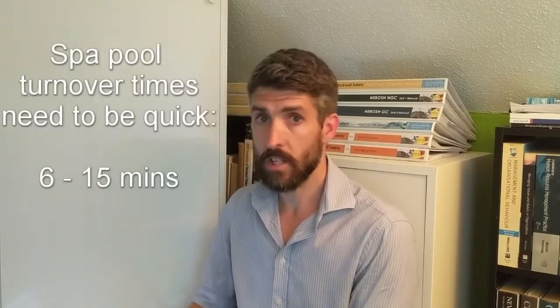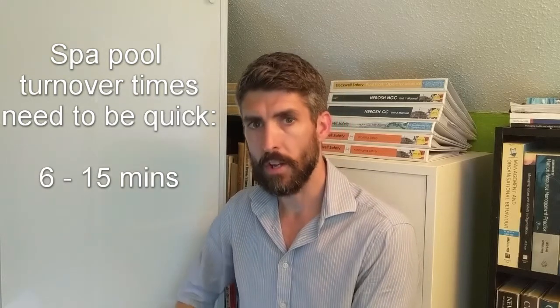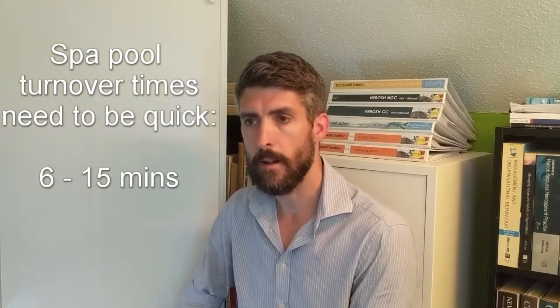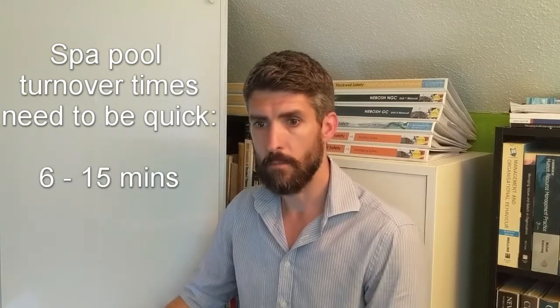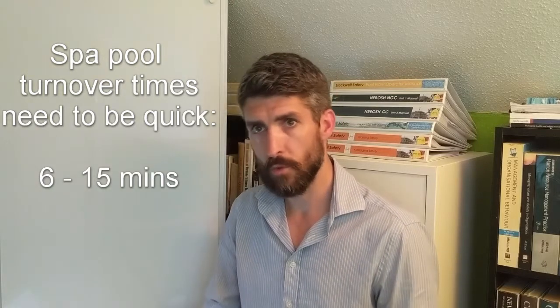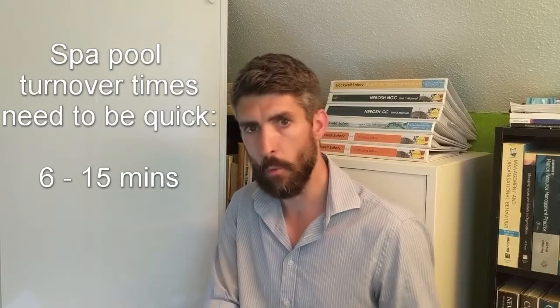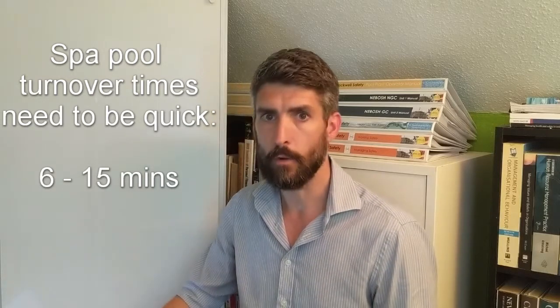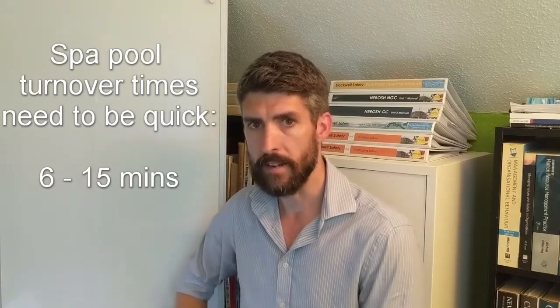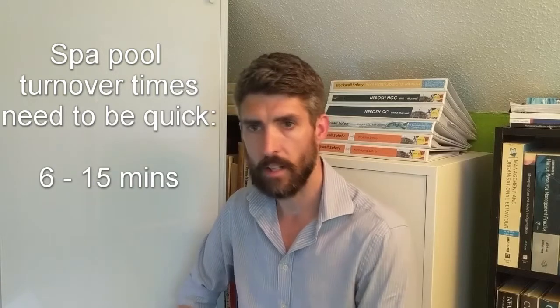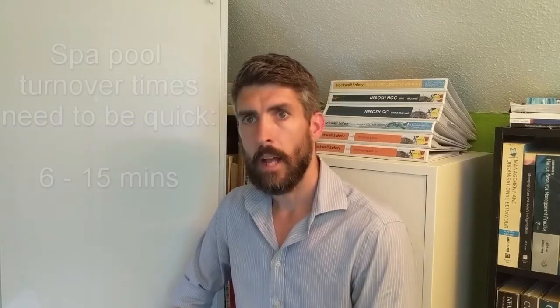What you're looking at for commercial spa pools is anywhere between 6 and 15 minutes. The busier the spa pool, the quicker the turnover time needs to be. The longer the turnover time, the more towards stagnant your water is becoming. And you don't want that. You want to get that water through that filtration system to keep it clean, fresh, safe, hygienic, relatively anyway.